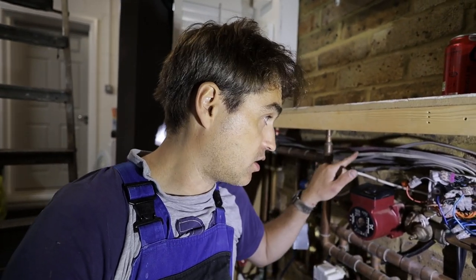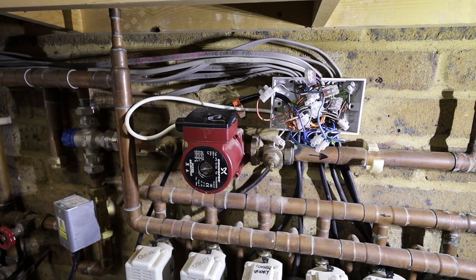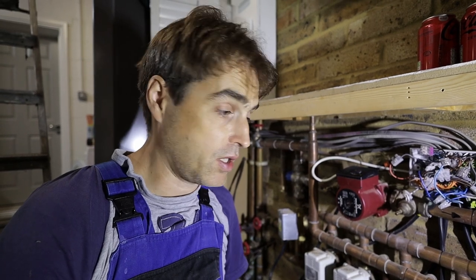I'm going through all the wiring centres, figuring out how they are wired and writing it all down. The wiring here is just room stat wiring — three-core and earth wires to every stat. Every stat has permanent live, neutral, switched live, and earth. Every stat can open one of the corresponding zone valves and fire the pump. They also fire a main zone valve — once one valve opens the pump fires, and that valve sends a switched live back to where the cylinders are on a three-core grey wire, going back to the boiler.